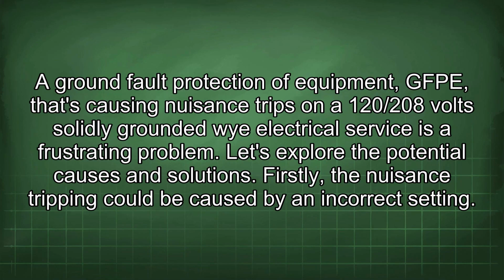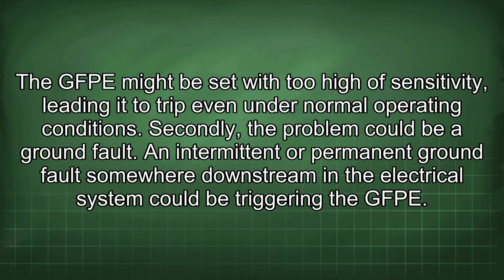Ground fault protection of equipment, GFPE, that's causing nuisance trips on a 120/208 volt solidly grounded wye electrical service is a frustrating problem. Let's explore the potential causes and solutions. Firstly, the nuisance tripping could be caused by an incorrect setting. The GFPE might be set with too high of sensitivity, leading it to trip even under normal operating conditions.